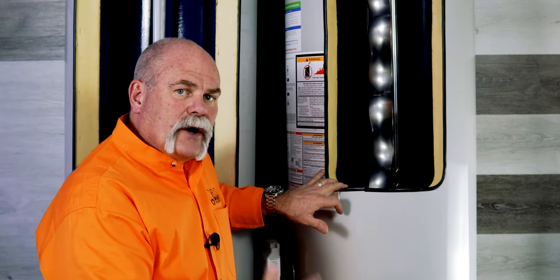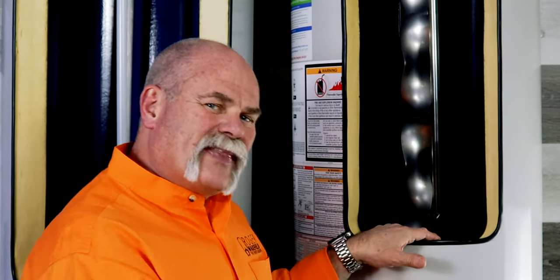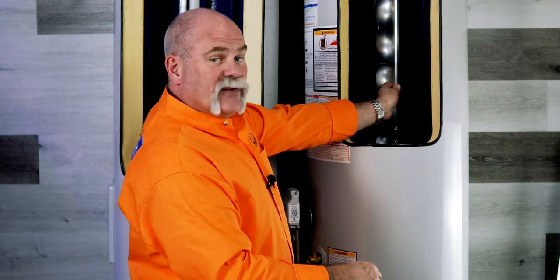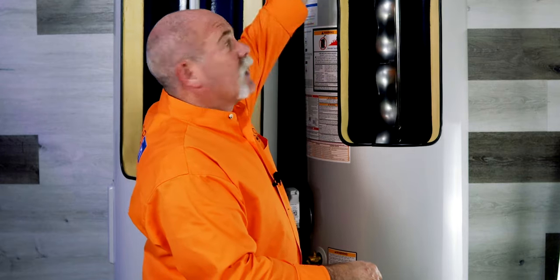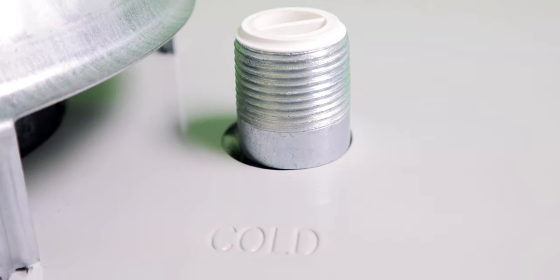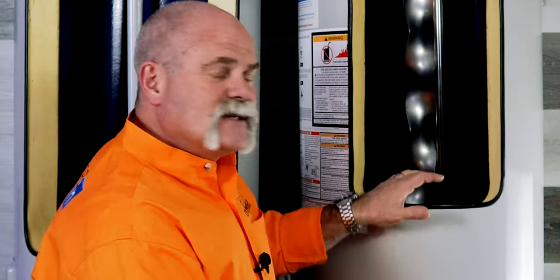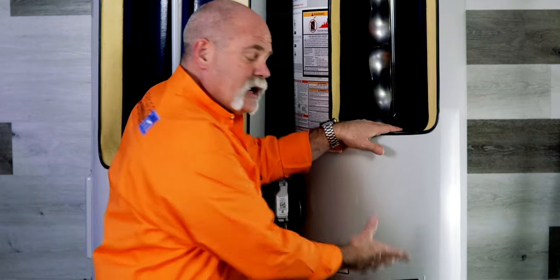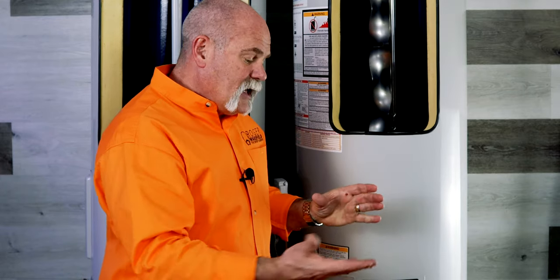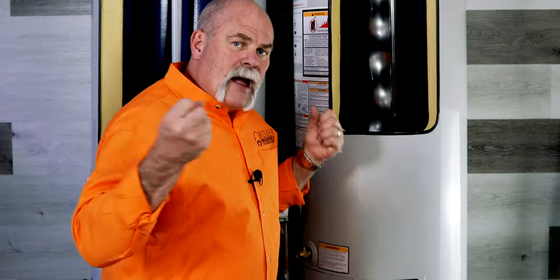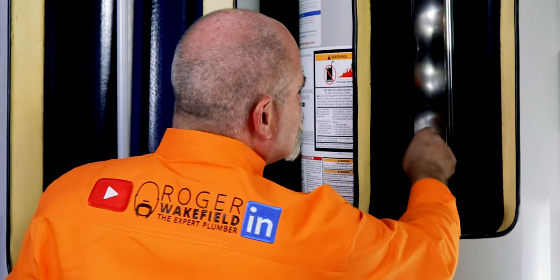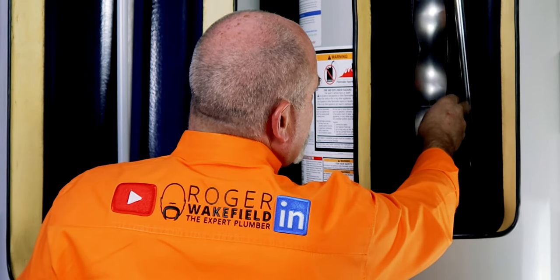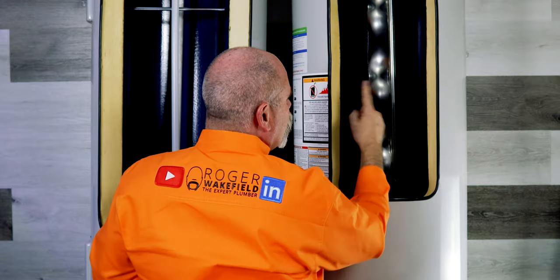Let me show you what's on the inside. I'll start with the gas water heater because there are a few more parts. The dip tube comes in on the cold water side and brings water down towards the bottom of the tank. The reason it does this is because heat rises. On the gas water heater you've got a burner assembly at the bottom, and when it kicks on it literally lights up a flame. Those fumes go right up the middle in this flue.